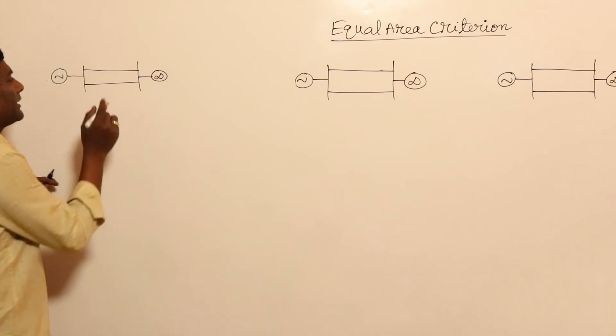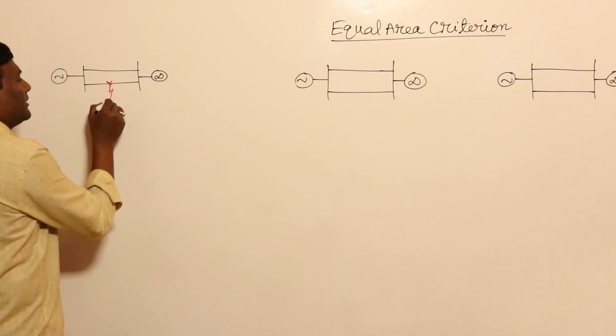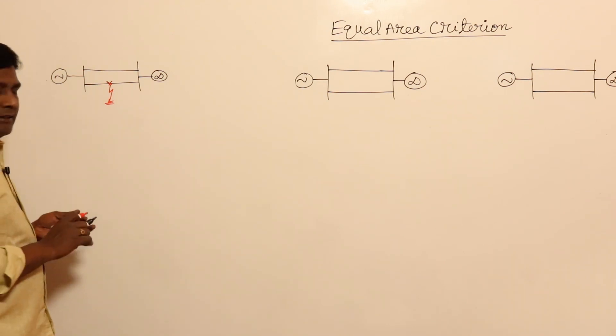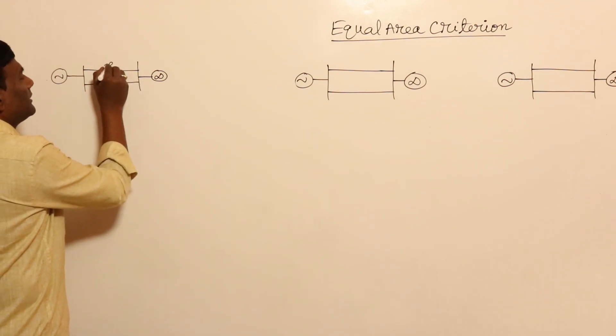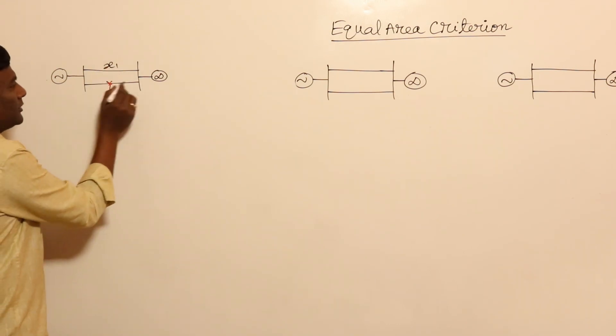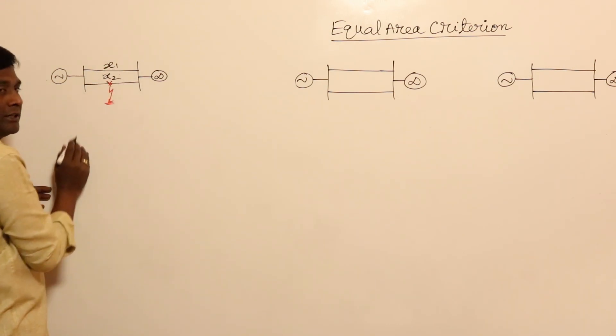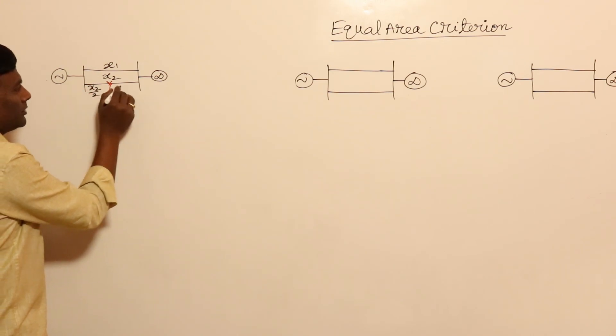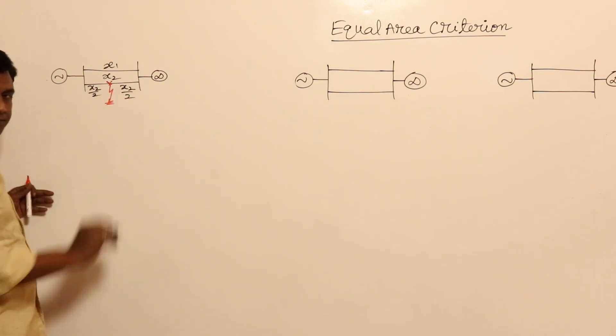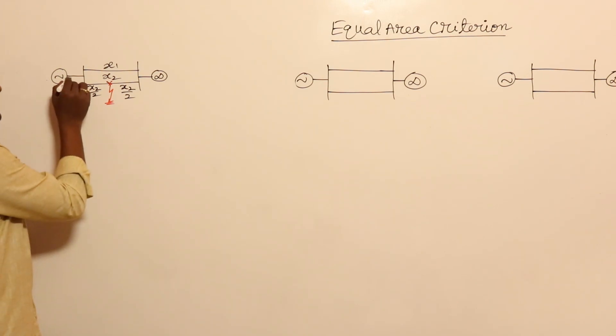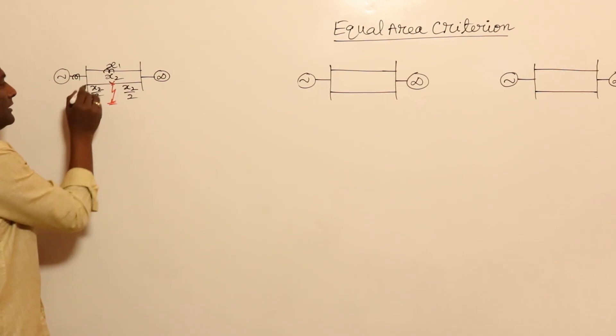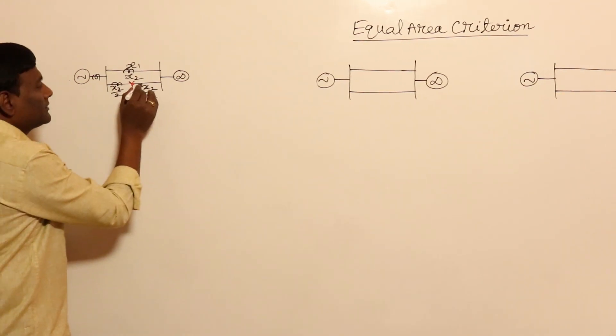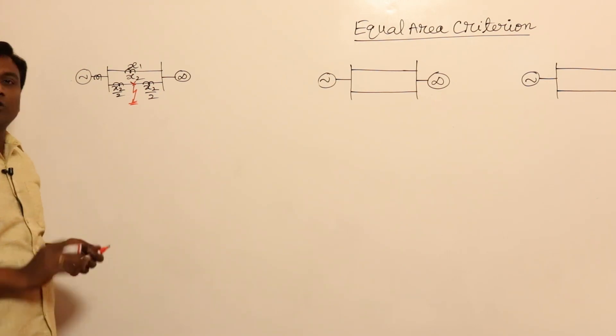In a double circuit line, if a fault occurs in the middle of the section, from here to here it is x1, and here to here this is x2. This means that this portion is going to be x2 by 2, and this portion is also going to be x2 by 2. So in this case, we have generator, generator reactance, and x2 by 2 as one reactance, x2 by 2 as another reactance, leading to the infinite bus.